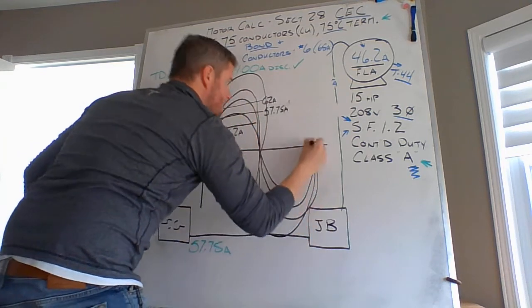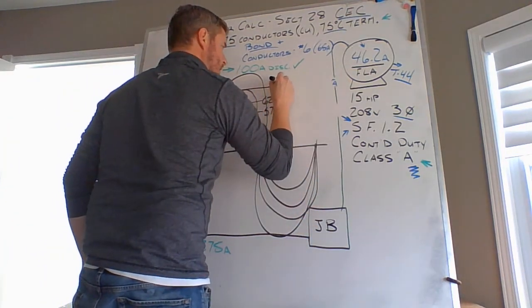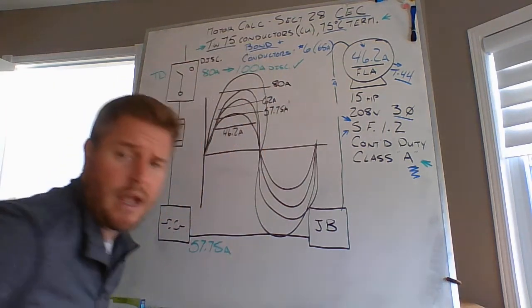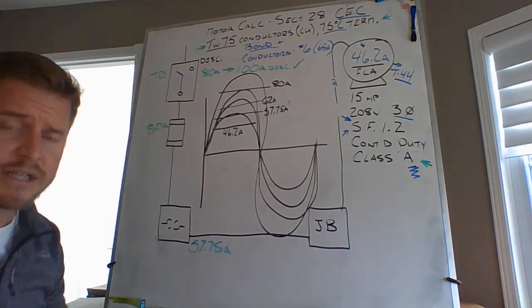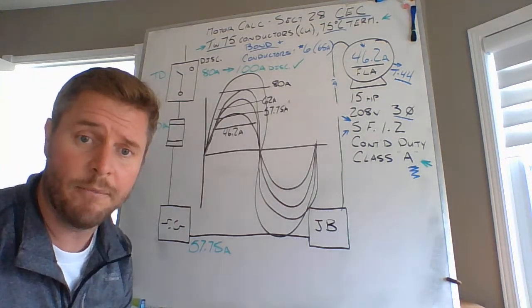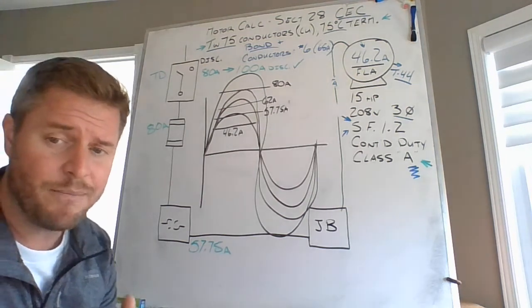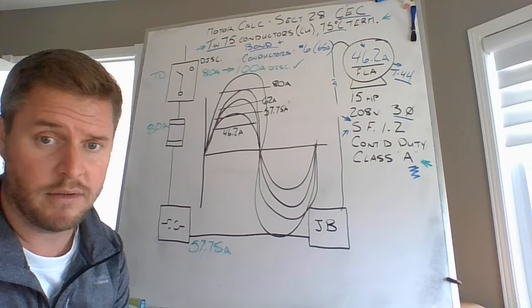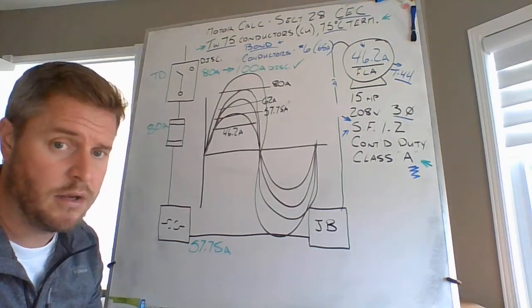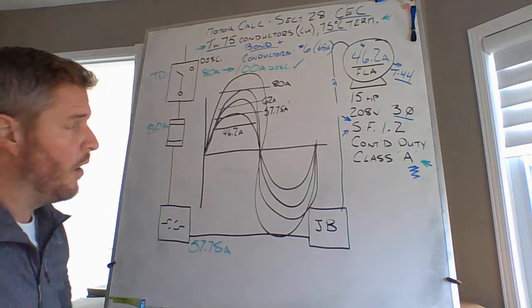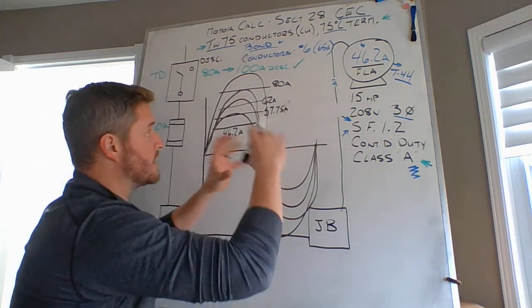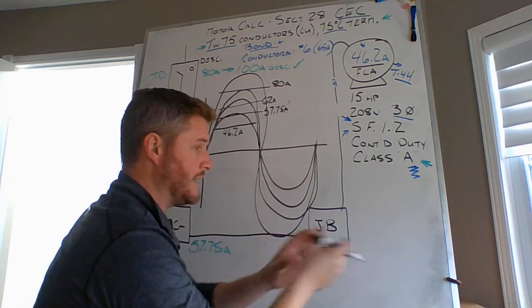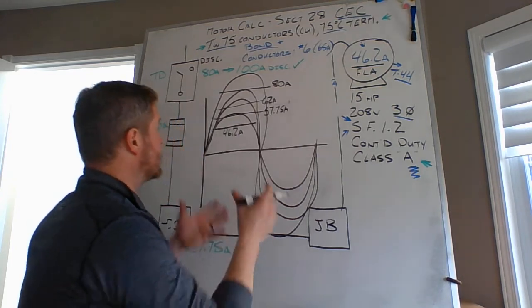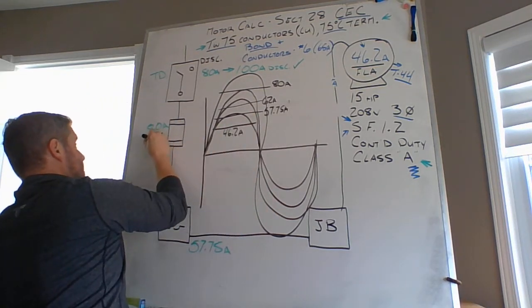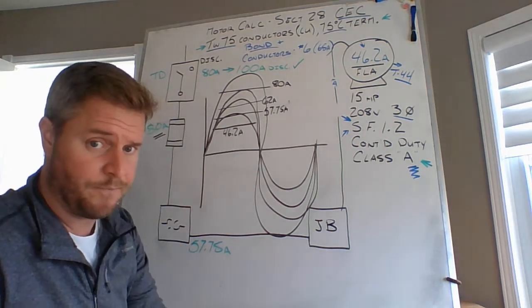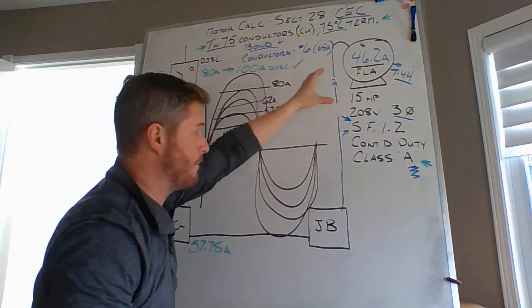to something like this, and it sees 80 amps as an RMS, it's still fine. It's still not going to open. It's a time delay fuse. It says, okay, you're drawing 80 amps for a little bit. That's fine. That's why I'm a time delay fuse. That's why you put me in a 100 amp disconnect. I'm going to let that current flow. Or if this was an initial startup and that motor decided it was going to go from 0 to 1800 RPM within a second or so, it's going to see an inrush in that current. And that's why we size these time delay fuses to be 80 amps, to provide that inrush current for that motor to get up to rated speed.